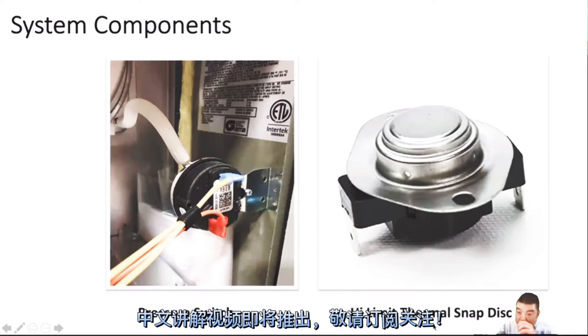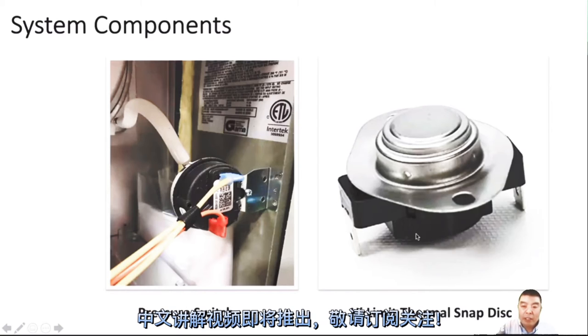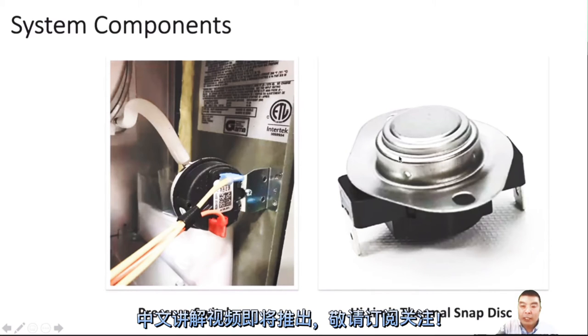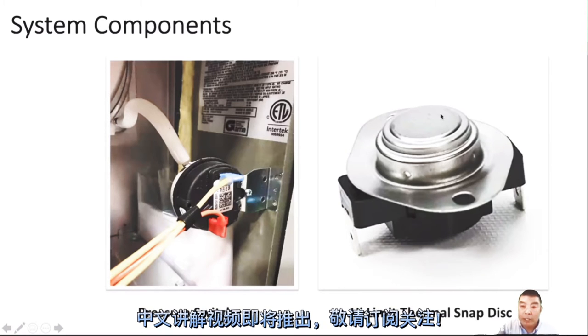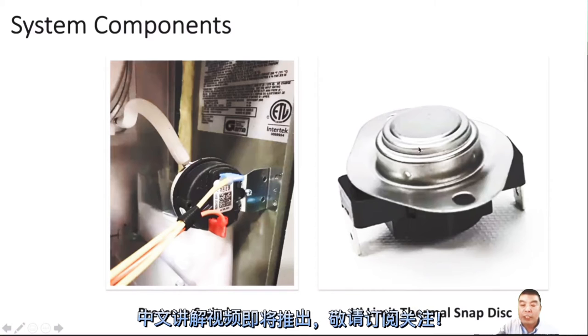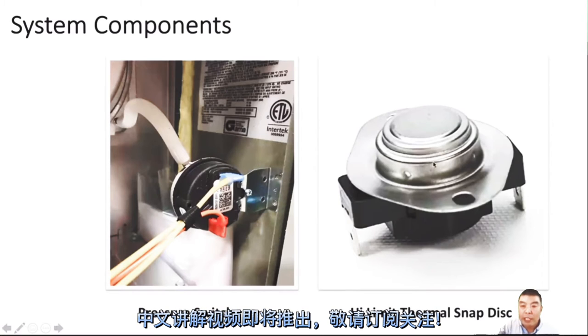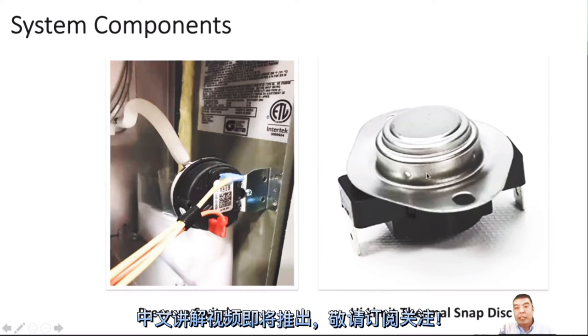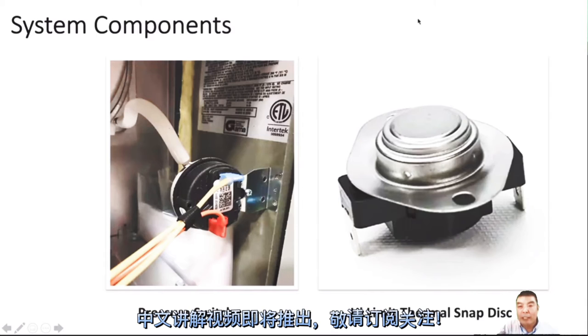The high limit thermal snap disk is one kind of high limit switch. This type is placed outside the cover, like a snap. There may be a small hole in the heat exchanger area — sometimes there is, sometimes there isn't — and it senses the temperature outside. Sometimes it is placed inside the heat exchanger with the sensor end going inside to sense the internal temperature. Another style is a long capillary-type sensor at the end of a tube. Different styles but the same function.